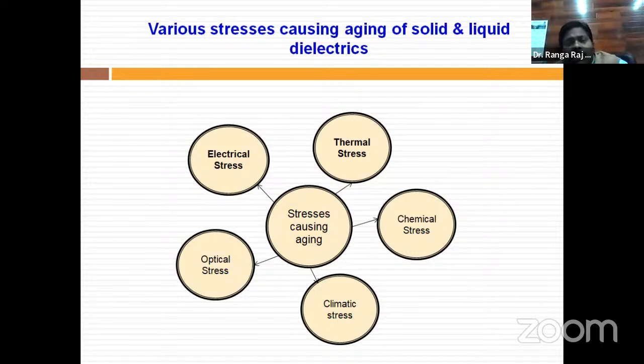Next dangerous stress is electrical stress. There are different conducting parts in every electrical machine, and electrical stresses are generated there. We have low voltage winding and high voltage winding in a transformer, primary and secondary, and there is a possibility of current forming between the windings as well as with the body, frame, yoke, and core. So we generally keep insulating paper or press board between the two electrical parts. If you don't keep this insulation, there is electrical stress and short circuits between the windings. So these two are the major stresses: thermal stress and electrical stress.